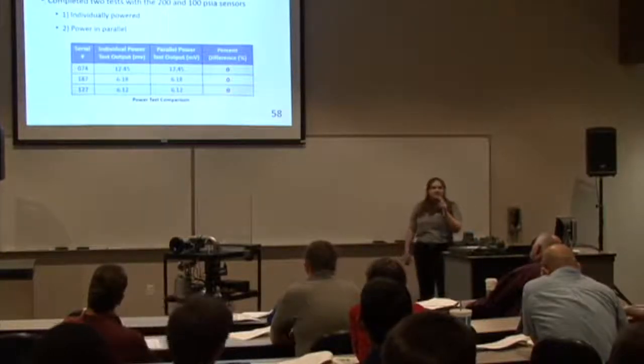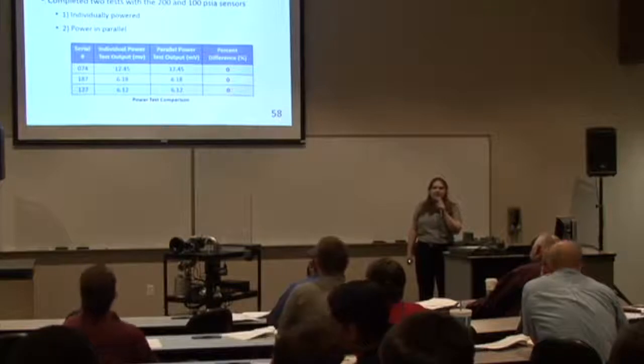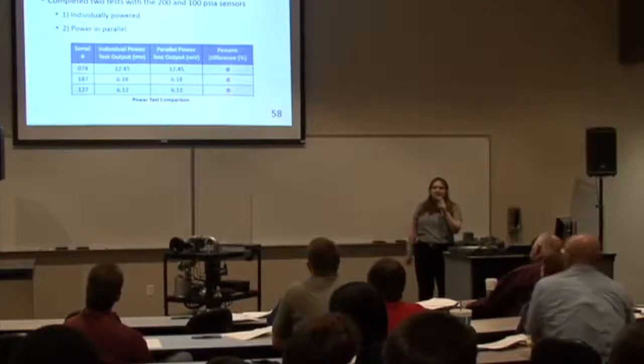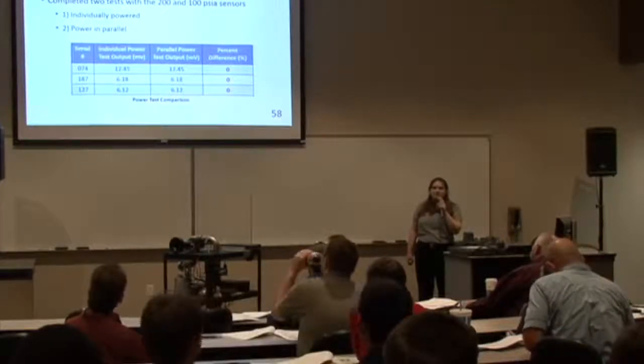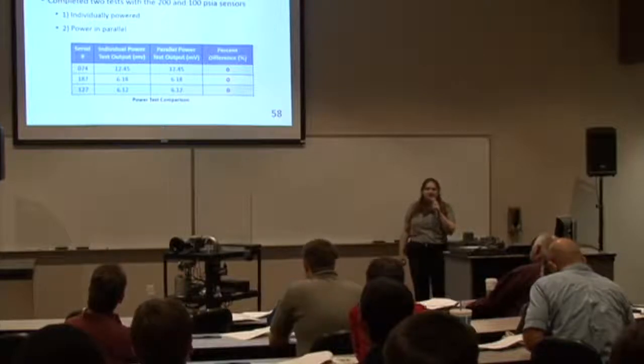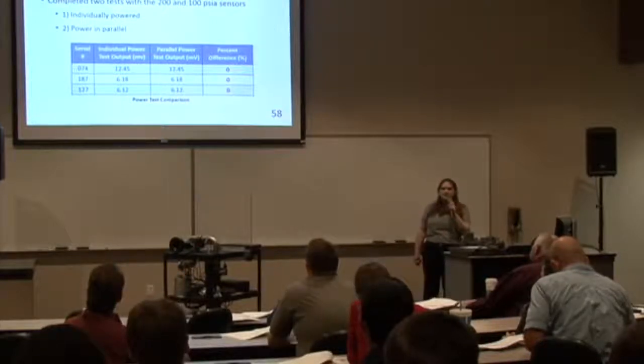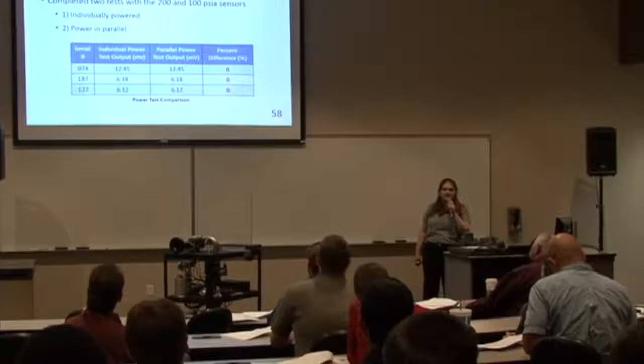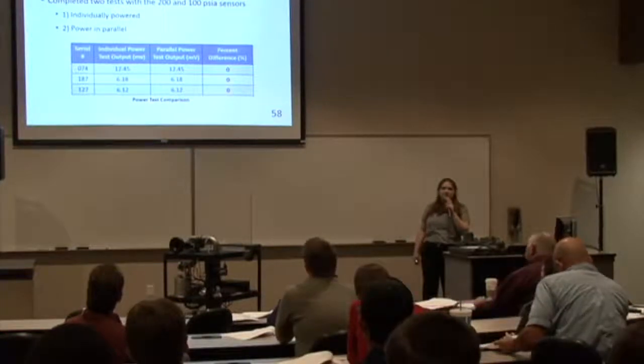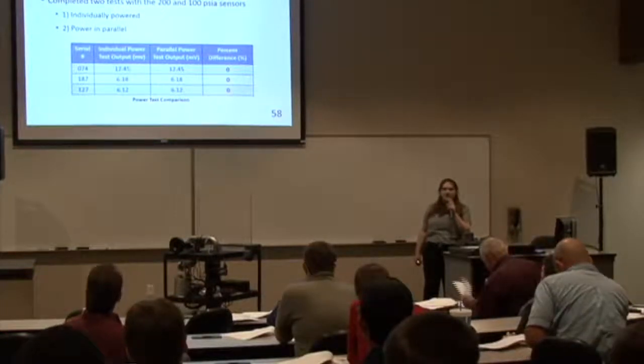At the beginning of the semester, we wanted to ensure that using one power supply wouldn't affect the data coming out of all 8 of our pressure transducers, so we did a parallel power supply test. This was done using two 200 psi sensors and one 100 psi sensor. Each was individually given 10 volts of direct current, and the output was read using a multimeter.